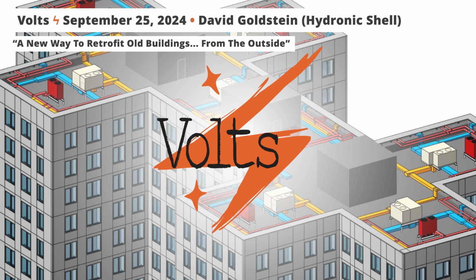So it is a central system, but it doesn't necessarily make sense to have one big central system. If you think about a building with a large footprint, and we'll be looking at large buildings, if you were to put one large heat pump in the center of the roof, it becomes a very big, heavy heat pump that requires a lot of structural support. But then you end up with a lot of distribution piping to get hot water and chilled water from that heat pump to all ends. It's also loud, and more complicated to operate and maintain.